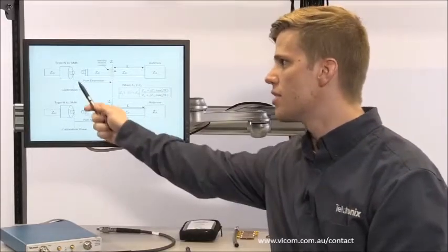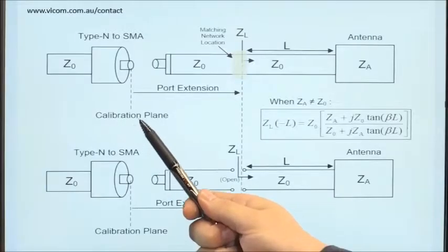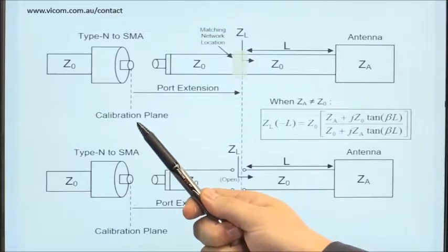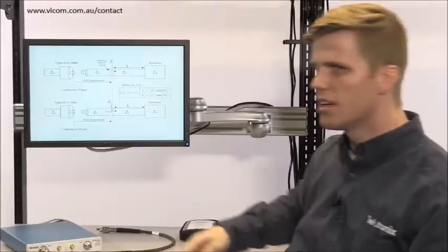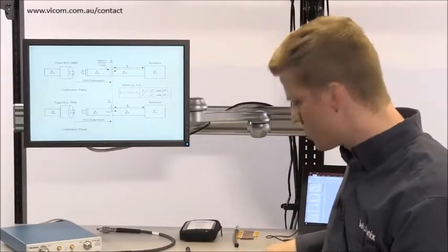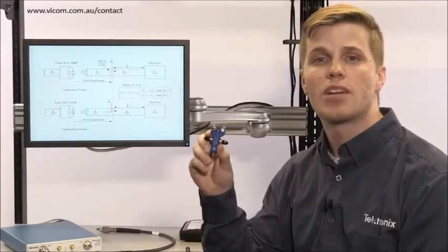The first step is to calibrate the VNA as close to the location of the matching network as possible. In this case, it's the end of the type N to SMA connector. And then to get the calibration plane to the location of the matching network, we're going to have to apply a port extension. So first, I'll calibrate using my type or my three and a half millimeter spinner cal kit at the end of the type N to SMA connector.